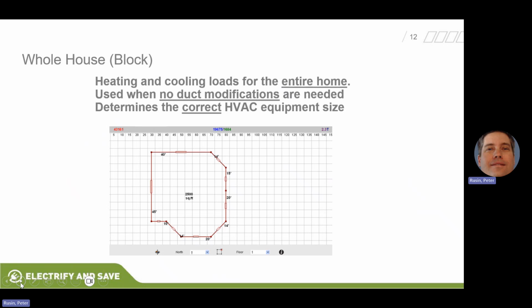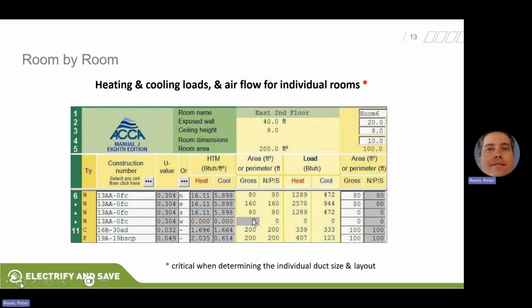It will give you the correct HVAC equipment size. If you decide to mess around with the duct size or a few different things, then go ahead and do a room by room. ACCA provides some tools for room by room, and it's critical in determining individual duct size and layout. If you're doing new construction, you probably want to do a room by room. In some cases room by room makes sense on retrofits, but we can also do block loads. You guys in the field can get a feel of what works for you, but that's where we start, mainly with the block load, and then go room by room if necessary.